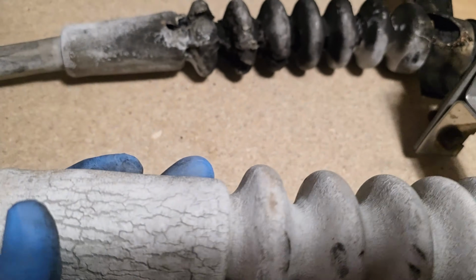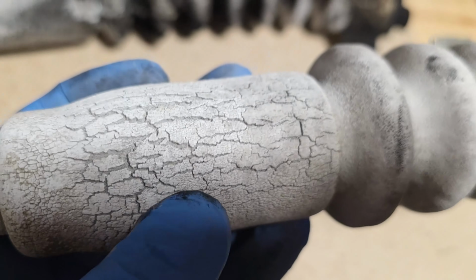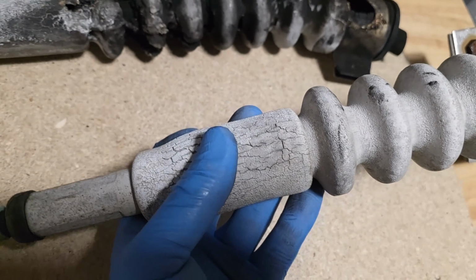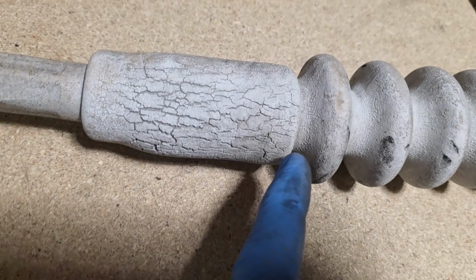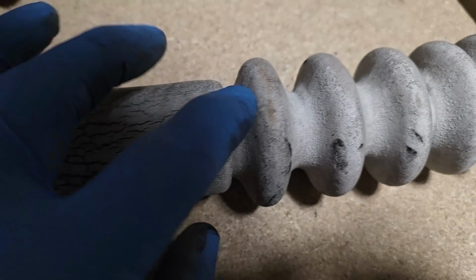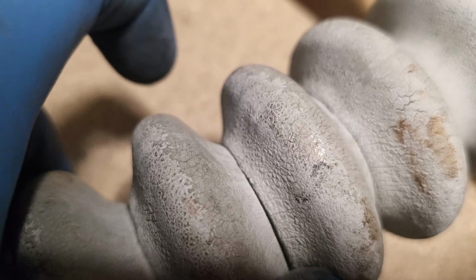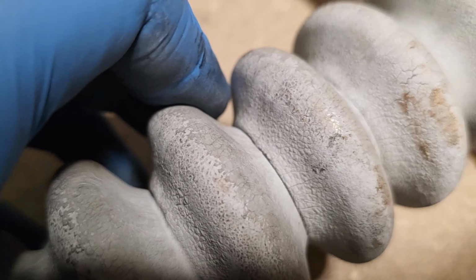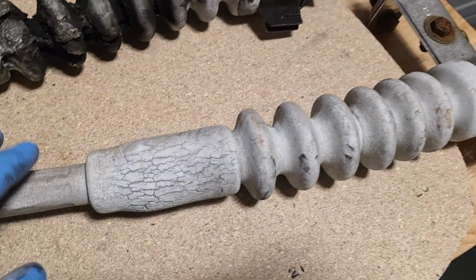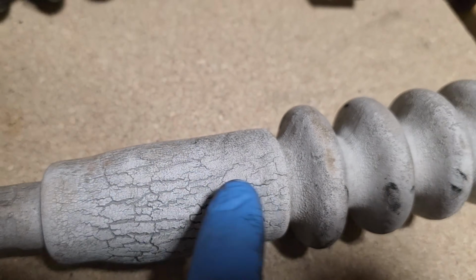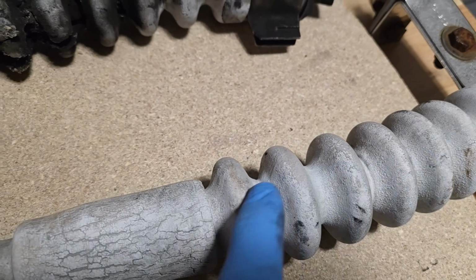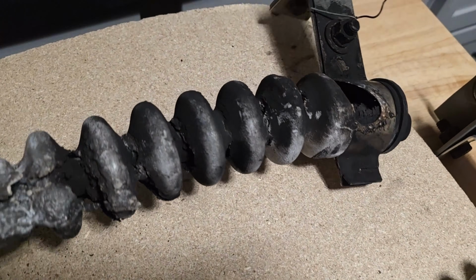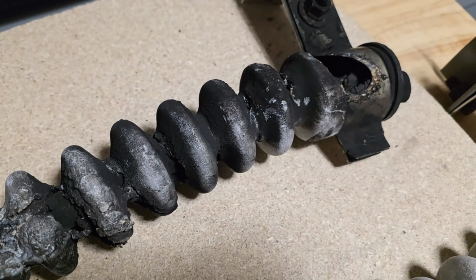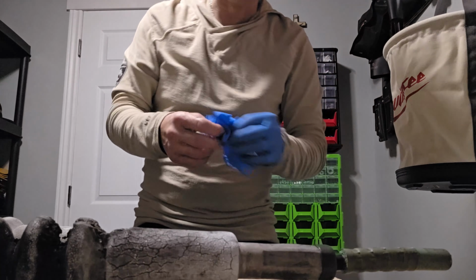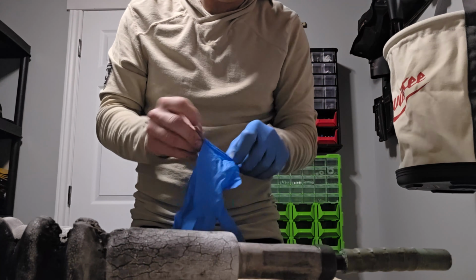Likely what failed in this cable, when you look at the condition, this here, when it gets all cracked, same as a crack in a porcelain insulator, the electricity at that point can, if the cracks are deep enough or if it's completely severed down to the inside, which that pretty much, yeah, that's completely separated. This was a good one. This guy was energized. It can break down to the point where it's constantly trying to establish a path, and then it just snowballs from there. So I'm just going to get my Sawzall out and we're going to cut that guy open.